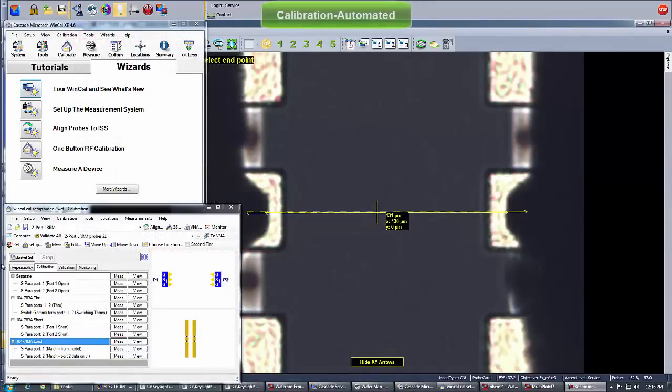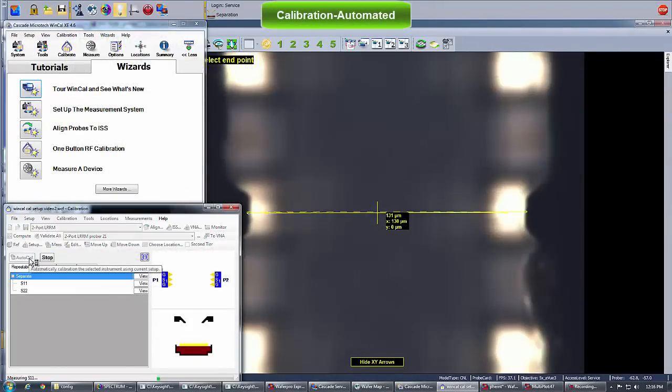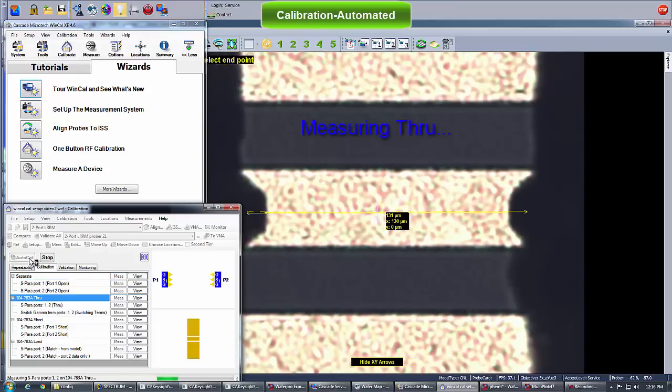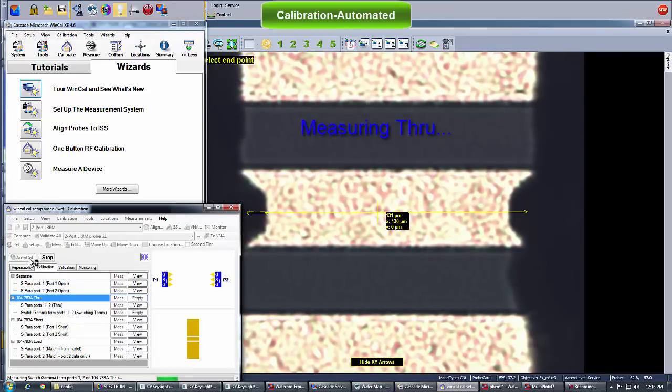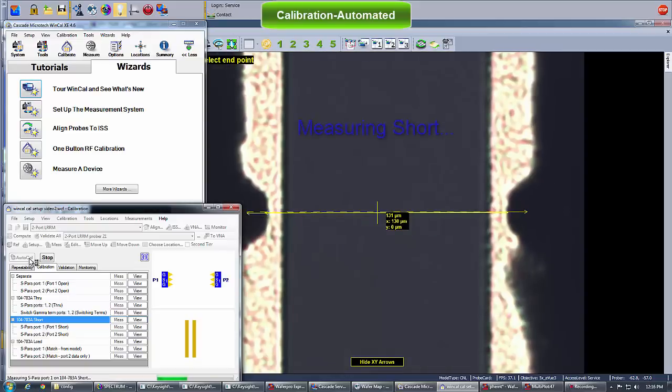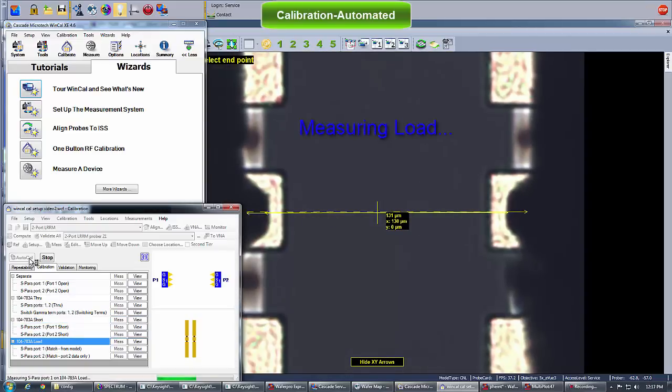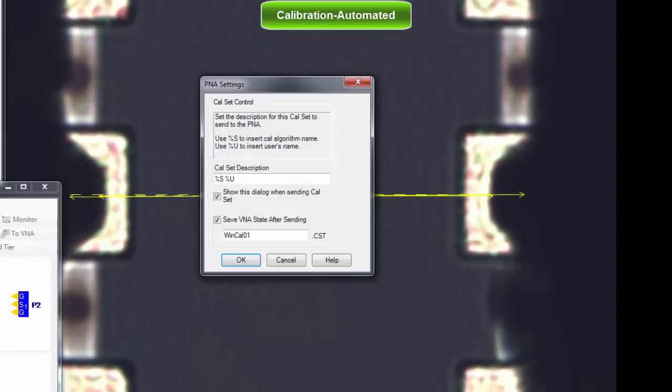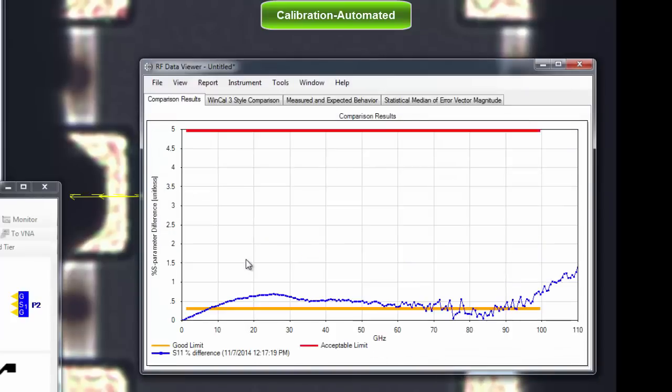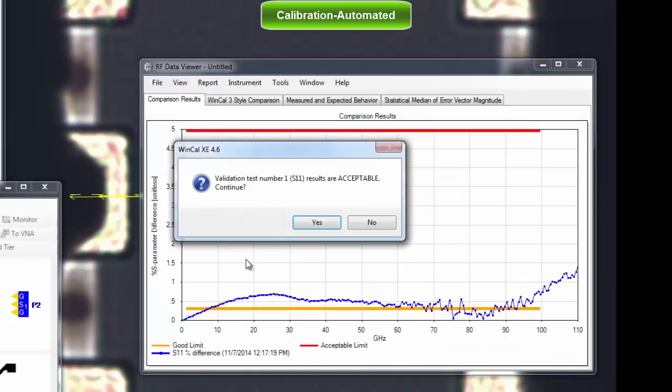I always recommend running the calibration automatically, especially above 50 GHz. The video clip in the background shows an automated calibration executed by Cascade WinCal software. WinCal steps to, contacts and measures each standard. Then it computes the calibration coefficients and stores them into the PNA. It also performs a first check of the calibration results based on known models of the standards and probes.